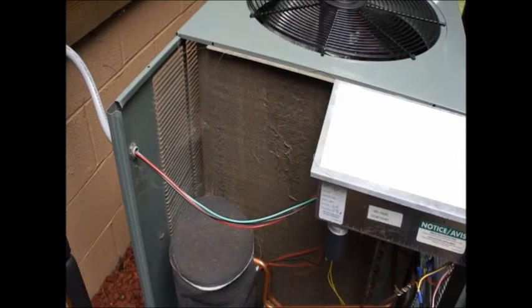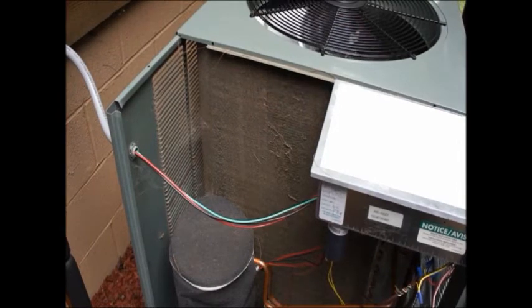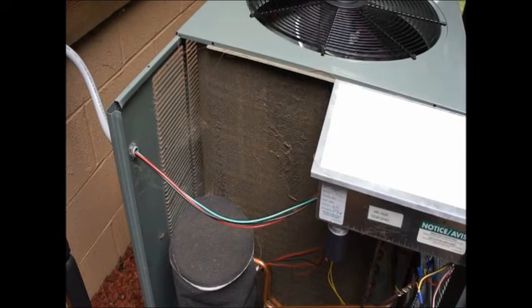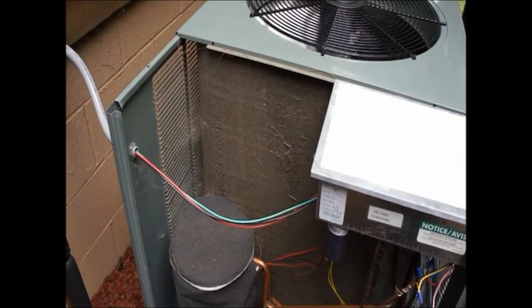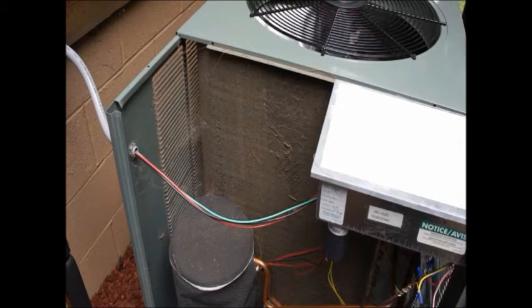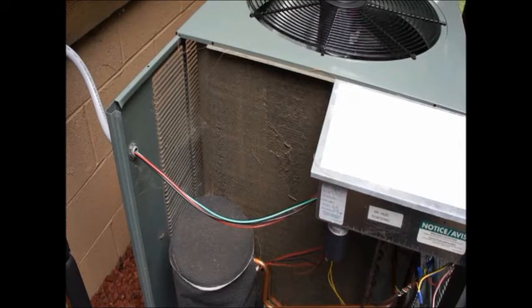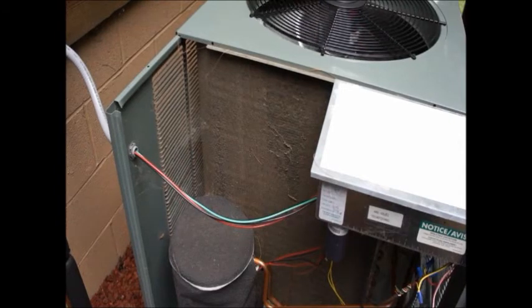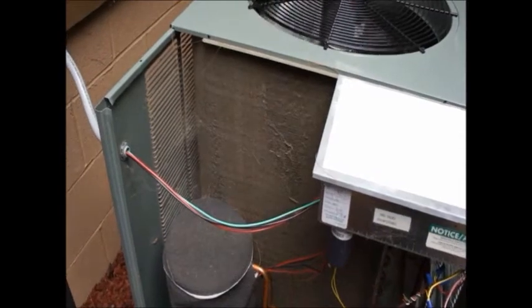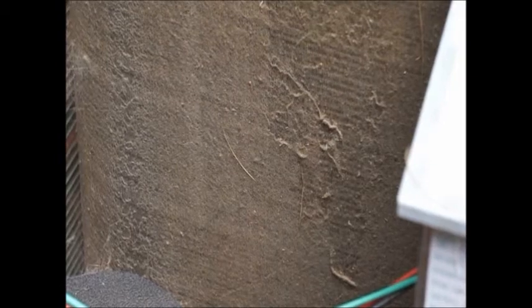This is my own 16 SEER unit. Believe it or not, I just put this in this spring. When I opened it up and took a look at the condenser coil, it's just plugged solid with cottonwood and dirt. We had a really heavy pollen season here in Ohio. So we're going to do a couple of recordings - a test in and a test out so we can actually take a look at the difference in the results.